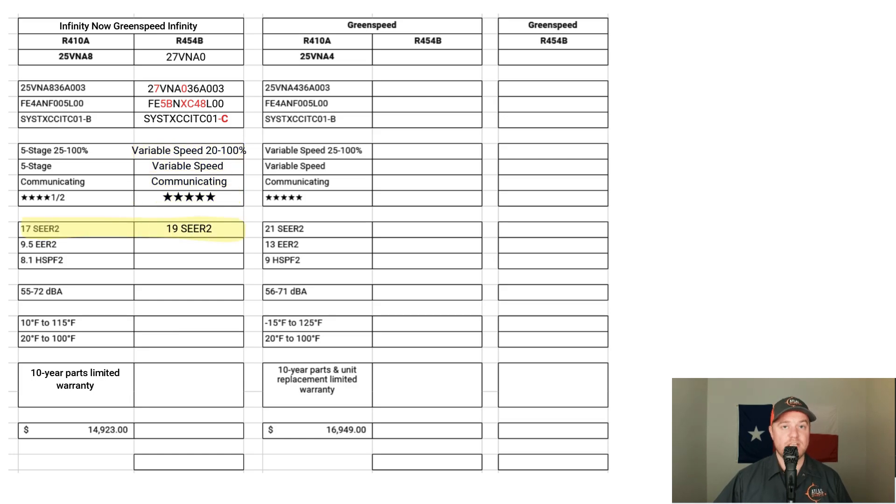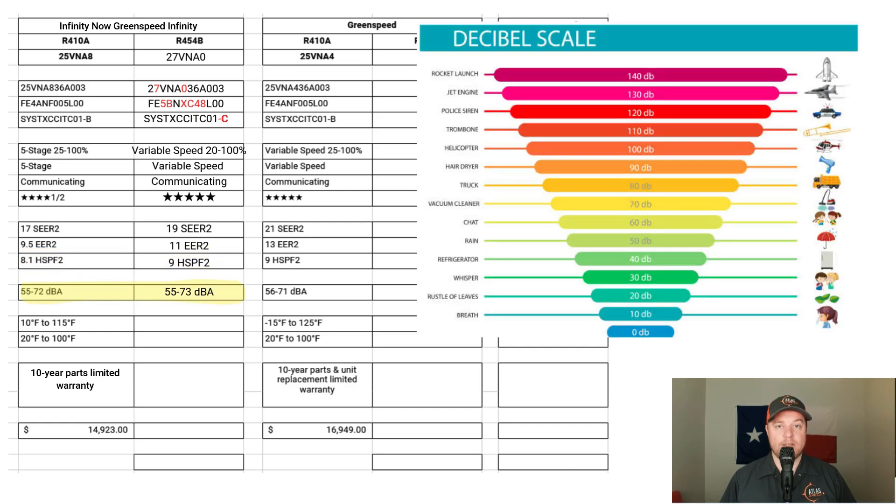Comparing efficiency: the five-stage delivered 17 SEER2, and the new fully variable speed delivers 19 SEER2 — a decent jump. The five-stage accomplished 9.5 EER2, while the fully variable accomplished 11 EER2. For heating efficiency, the five-stage delivered 8.1 HSPF2 and the fully variable delivers 9 HSPF2. So the new R454B system is quite a bit more efficient. For sound levels, when the five-stage operates in lower stages it runs around 55 decibels, and at 100% capacity around 72 decibels — very similar to the 27VNA-0, which operates between 55 and 73 decibels.